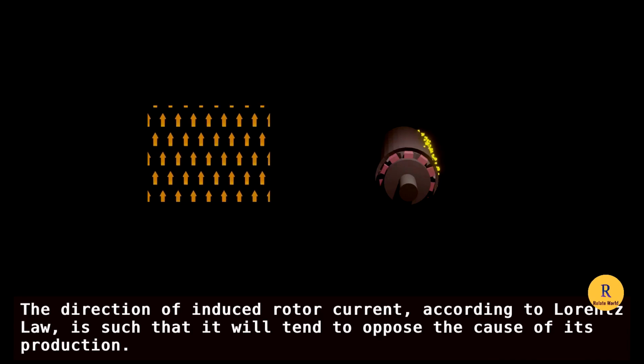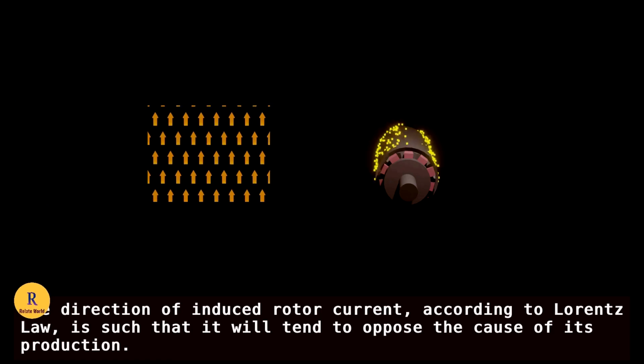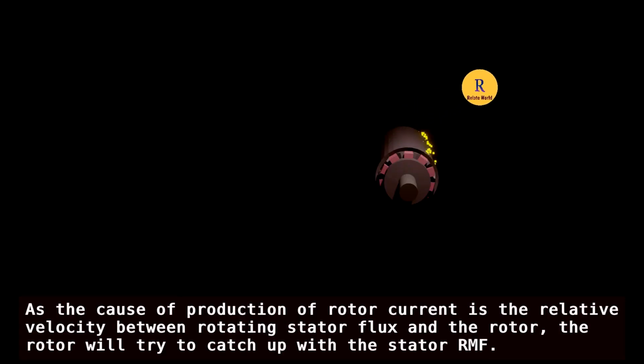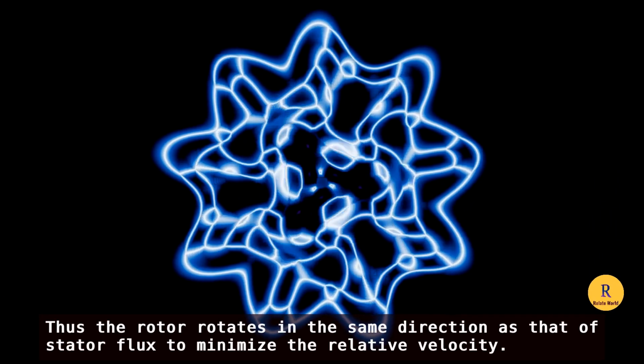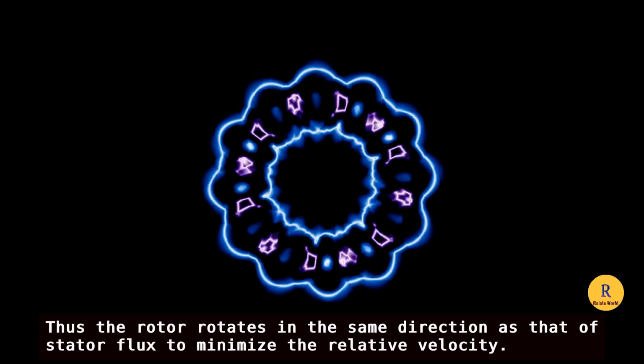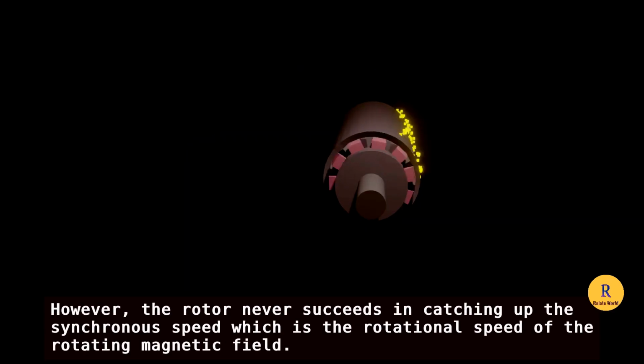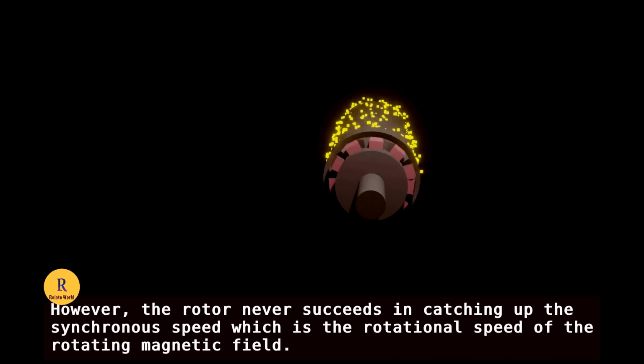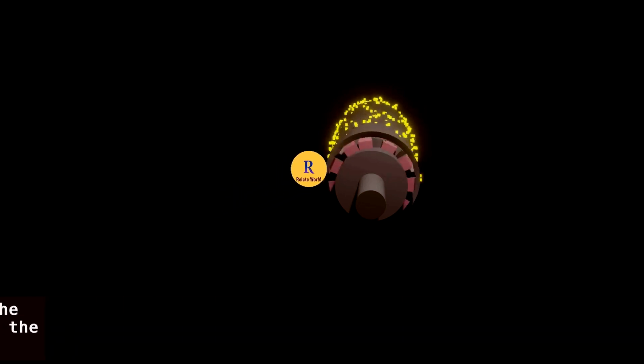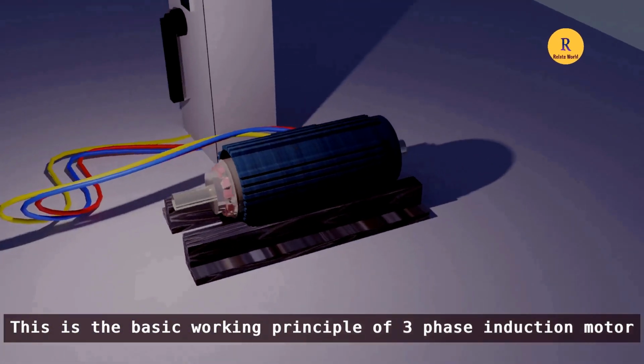The direction of induced rotor current according to Lenz's law is such that it will tend to oppose the cause of its production, as the cause of production of rotor current is the relative velocity between the rotating stator flux and the rotor. The rotor will try to catch up with the stator RMF. Thus, the rotor rotates in the same direction as that of the stator flux to minimize the relative velocity. However, the rotor never succeeds in catching up with the synchronous speed, which is the rotational speed of the rotating magnetic field. This is the basic working principle of a three-phase induction motor.